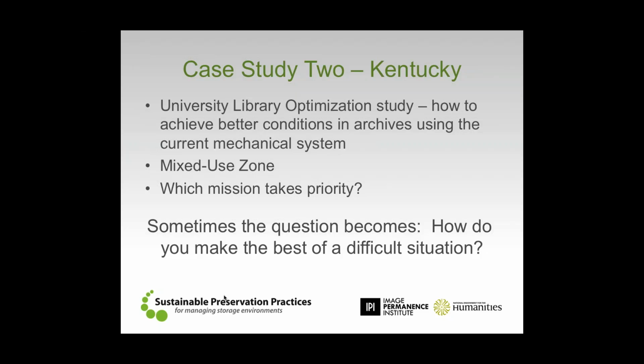But in the long-term case, you're trying to do 2 wholly separate missions or 2 wholly separate mandates with one piece of equipment, and it can't achieve either one of them efficiently. This is one where, even though there were some ways to improve it, in order to really get to the best operation for both spaces in the long term, this unit needed to be split in 2, and it needed to have separate units managing both, one for the archives and one for the occupied space.